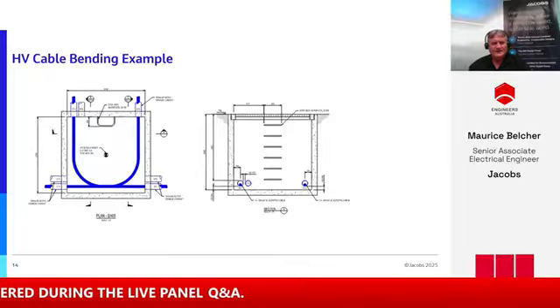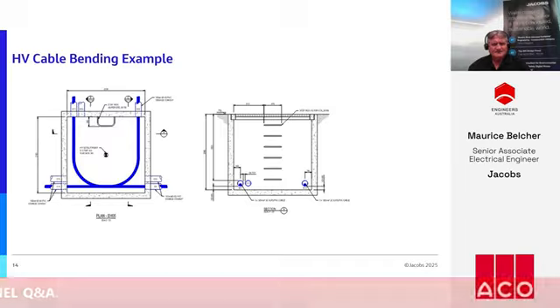So this is a snapshot of an HV cable pit, shown out of specification, specifying this particular pit from a plan perspective on the left hand side and an elevation on the right hand side. Key things to note are the size, it's rather large, and the ladder and access lid. There are multiple versions that could be used for that lid - as discussed earlier, it could be multiple smaller panels, or one heavier panel with a small access penetration. So there's lots of variations there.